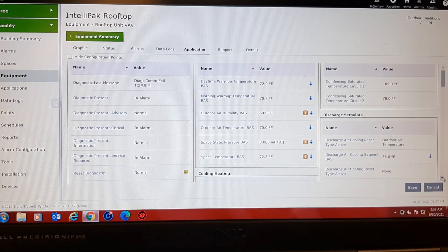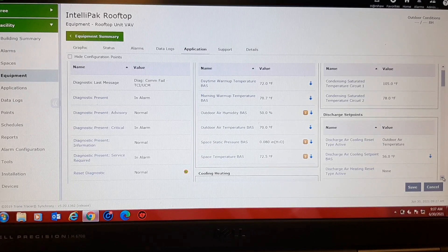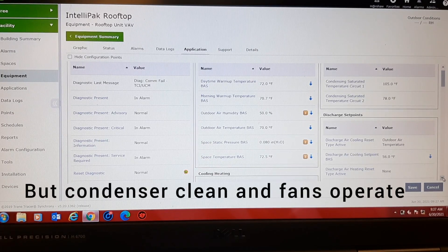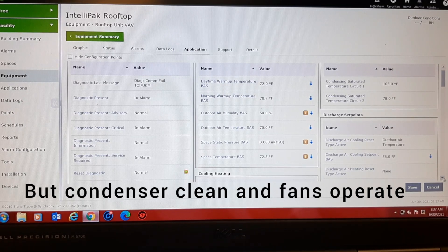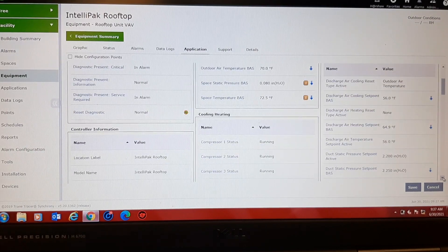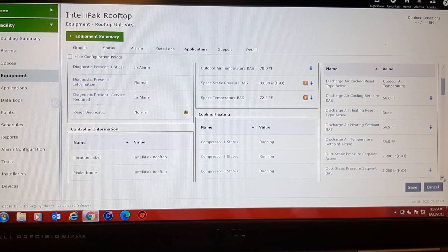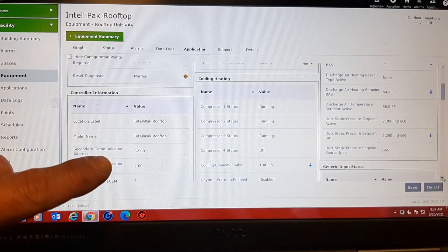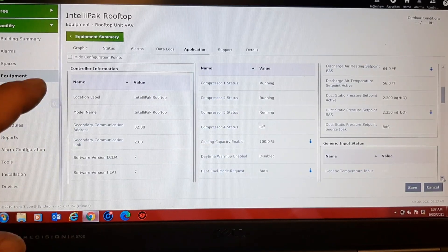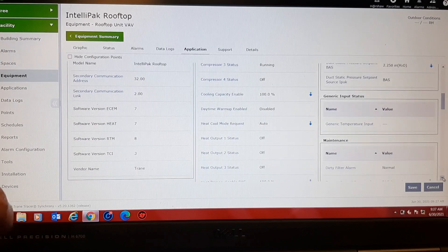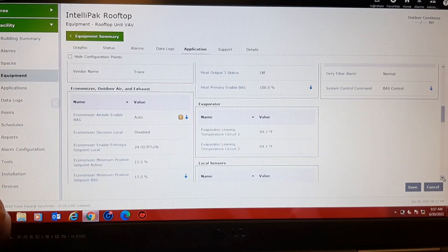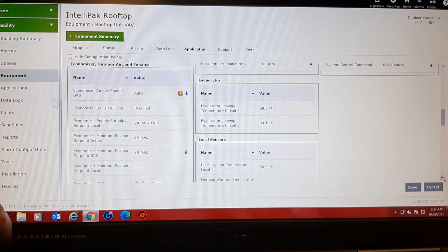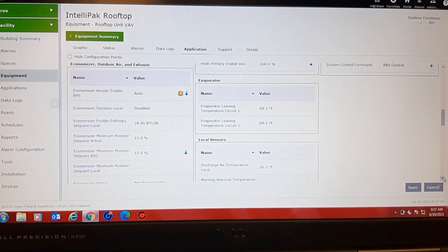The only difference in variable that may be an issue is the temperature outside. Because it's much cooler today and this morning. It's the same thing we basically looked at on the roof. Circuit 2 is down a compressor so that temperature is going to be higher.